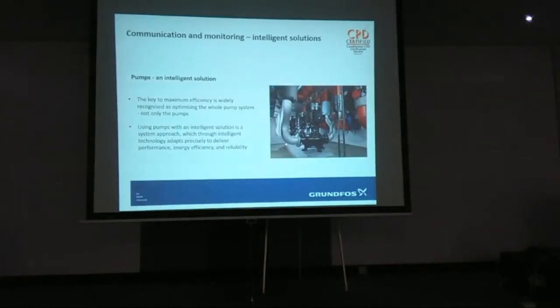Thinking of a pump as just a fan in a bucket, which I mentioned earlier on, really is the wrong way to do it. You do need intelligent information. What's the power absorbed? What's happening with the bearings? What's happening with temperature within the pump? Hours run, fault conditions and things like that. All of those can be built into electronic pumps. A lot of you will see our TPE and Magna ranges, where all of this information is on the screen or can be extracted by BACnet or Modbus, which is the normal sort of stuff nowadays.